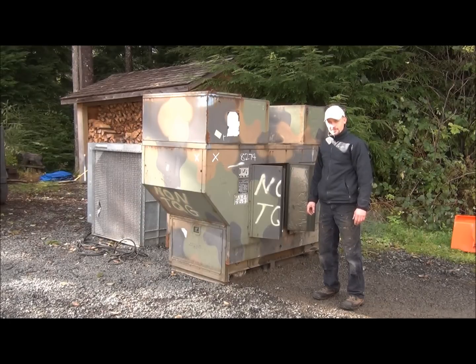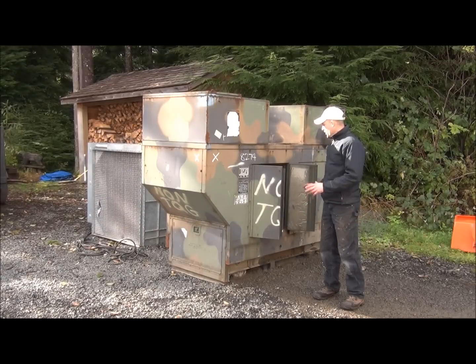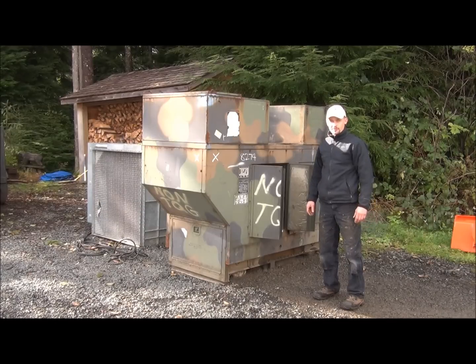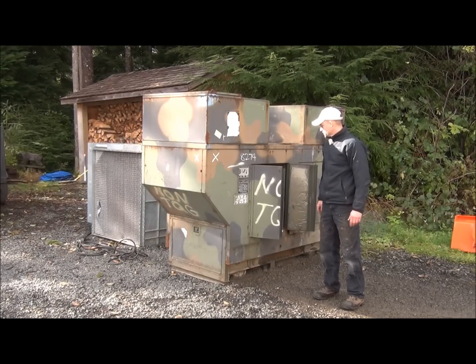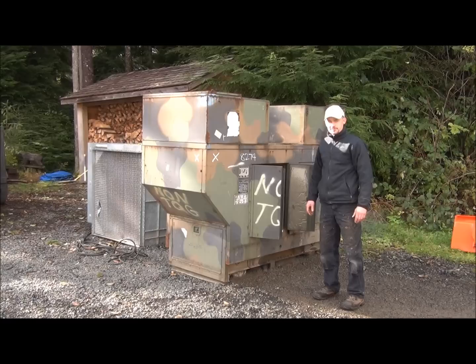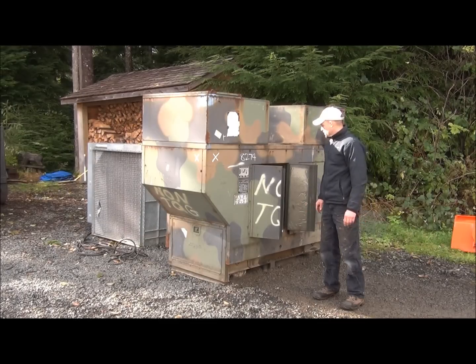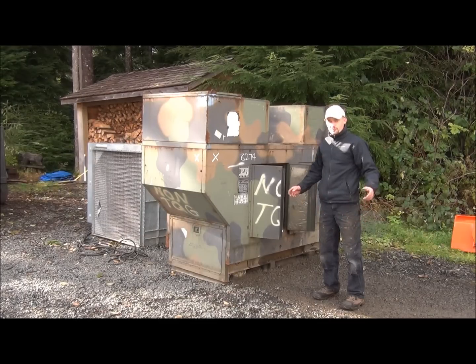What I'm going to do now is start it up and let it run for a few minutes. And I'm going to take just a walk around and look for anything out of the ordinary. I'll be looking for water leaks, oil leaks, checking the head gasket, see if I have any seepage coming out of there. Same thing with the valve cover gasket. I'll also be watching the fuel lines, fuel filters and oil filter, check and make sure I don't have any leaks coming out of those canisters or any of the external lines. I'll also be watching just for anything unusual. Any kind of sparks, noises, smoke, strange smells, anything like that.